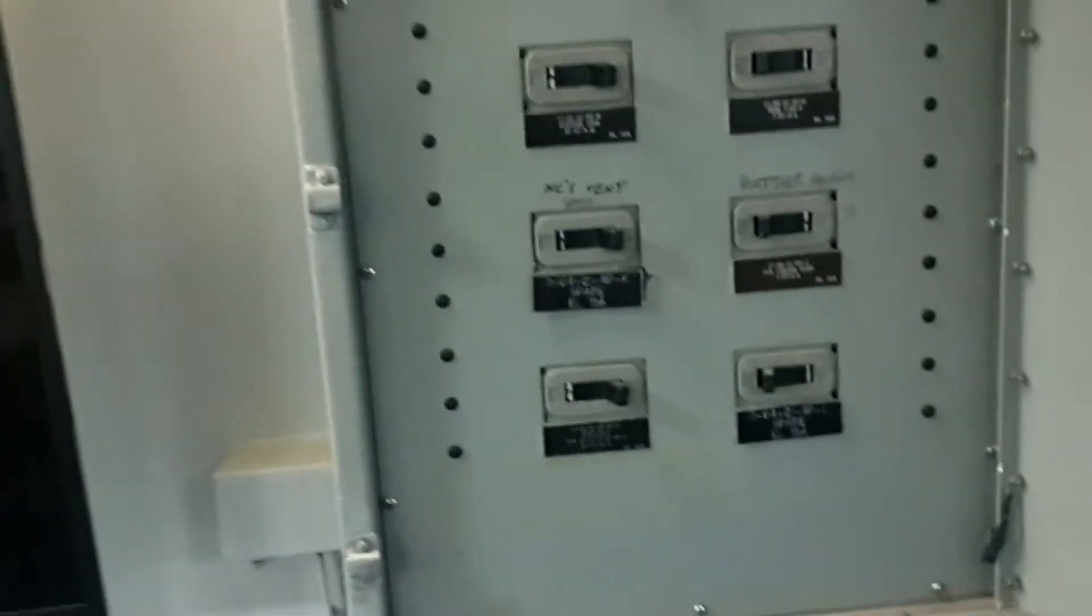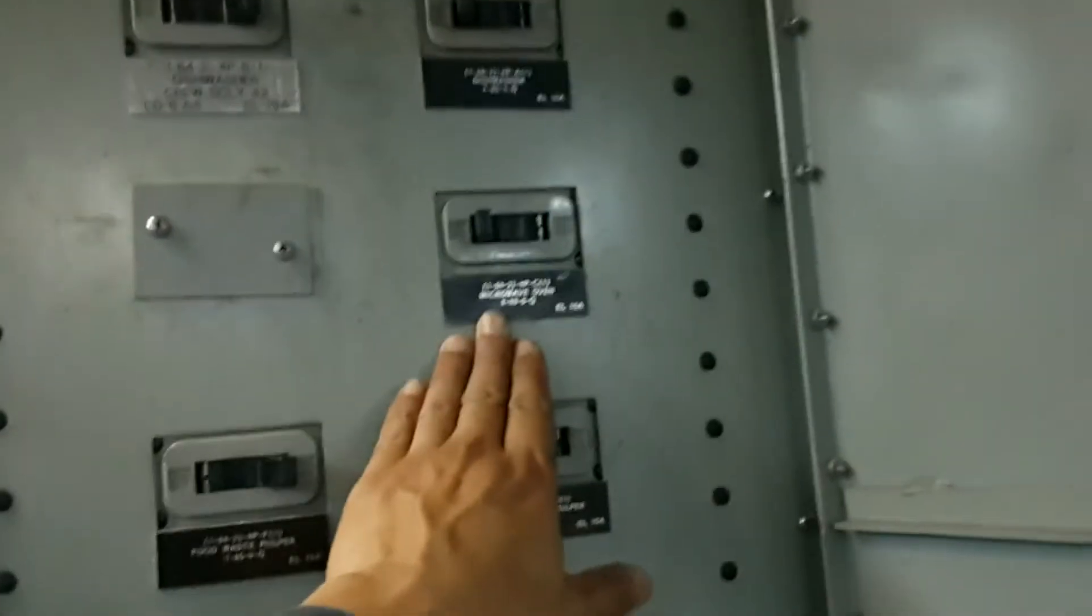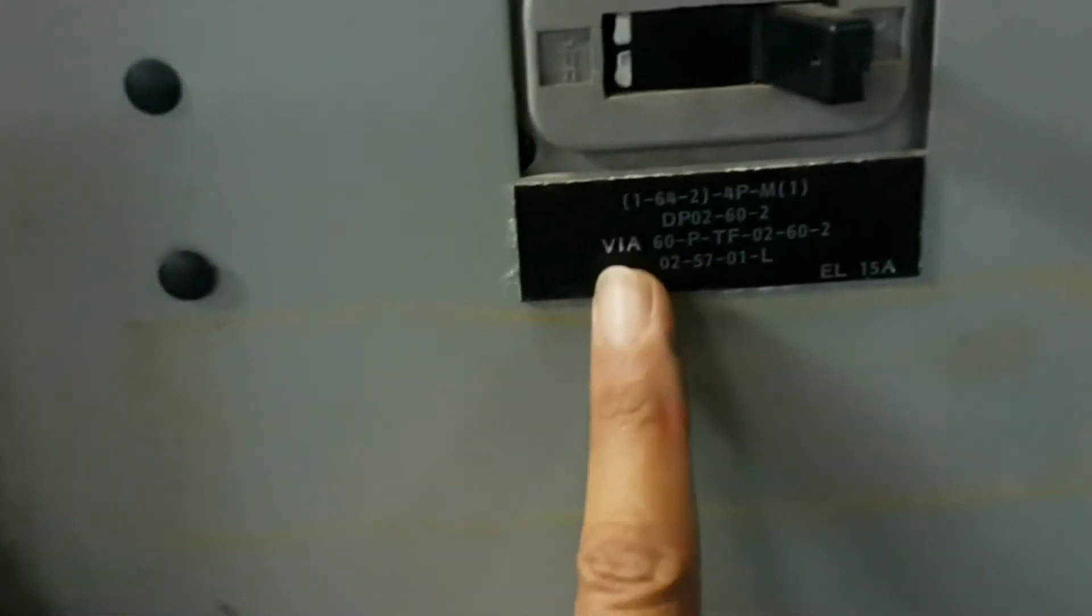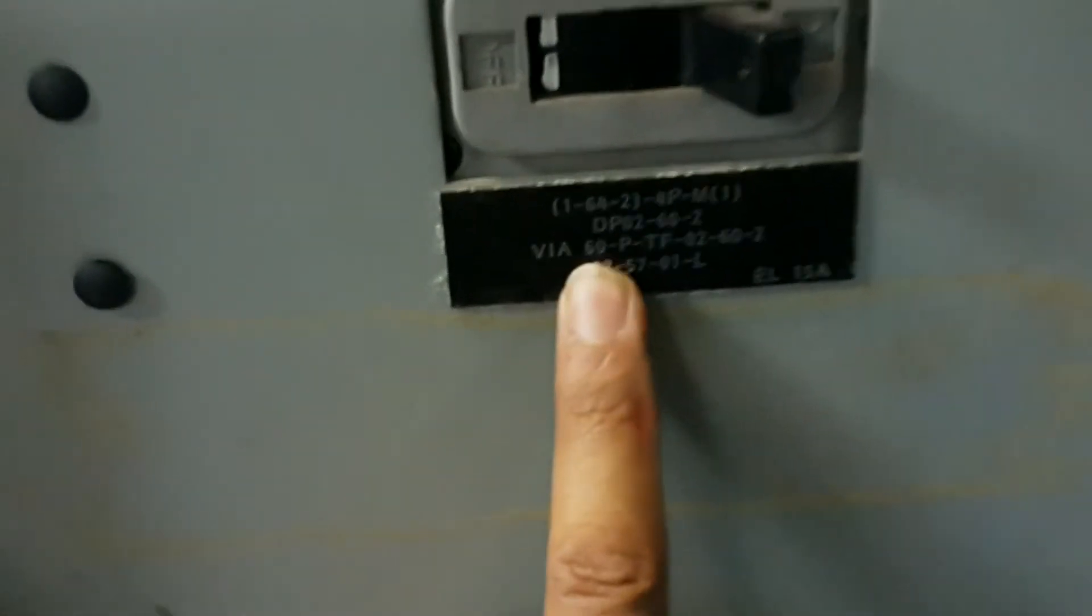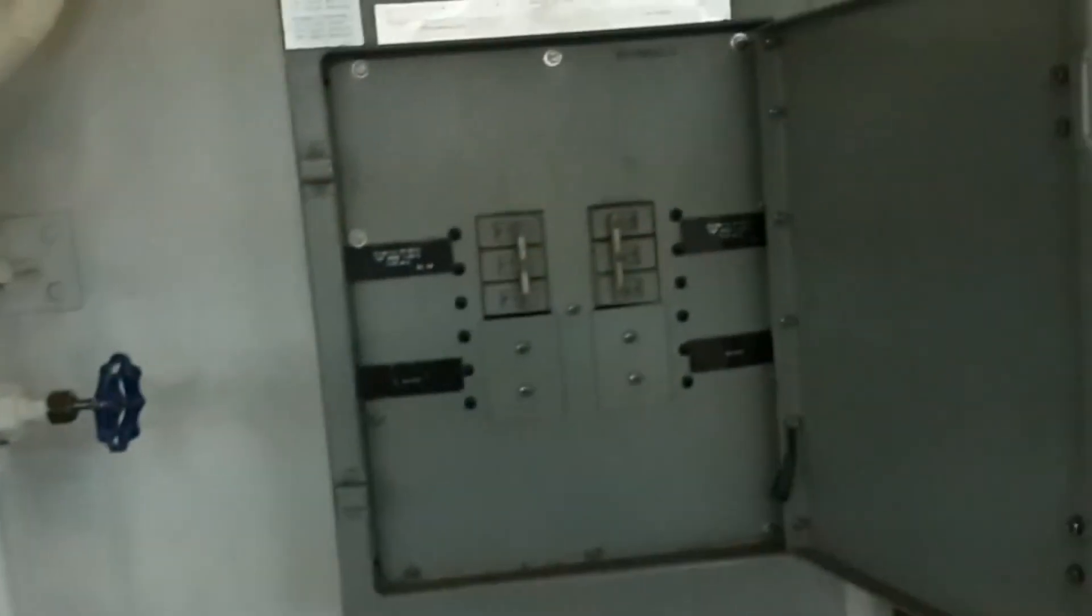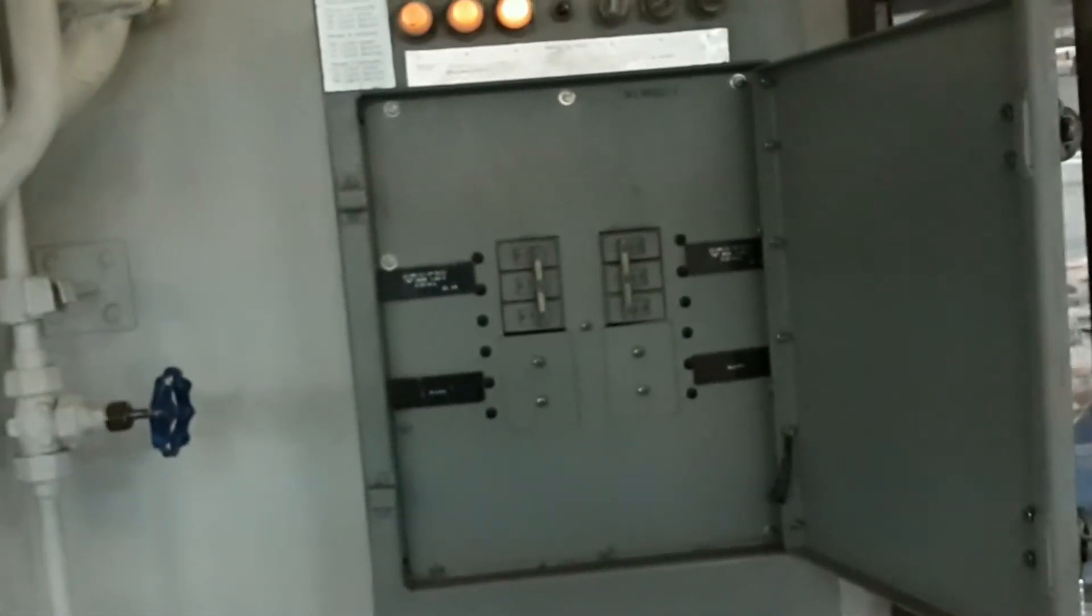Load centers typically feed power panels. Here's the power panel. The loads on the power panel are much smaller. Some of these loads are equipment itself, like this one happens to be a microwave. But this breaker, in particular, it feeds what is called a distribution panel, which means it's a smaller power panel, like this little guy. So, power has been cascading all the way from the switchboard, to the load center, to the big power panel, to this little power panel.